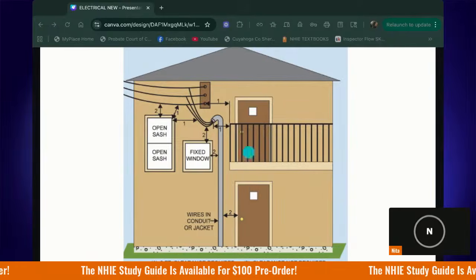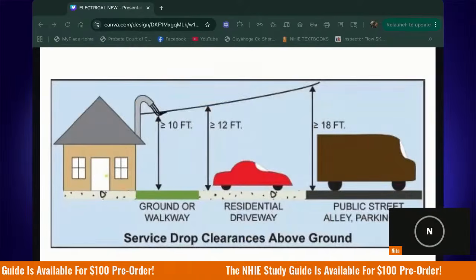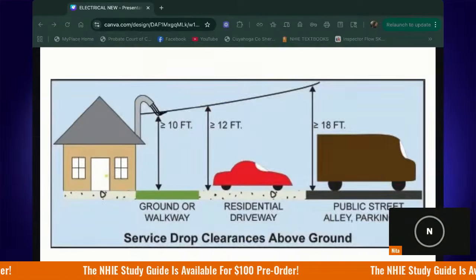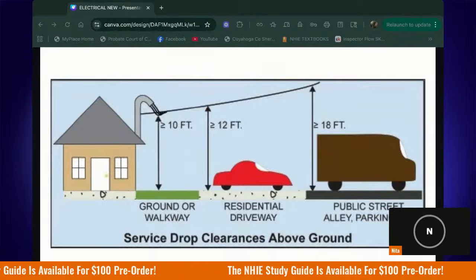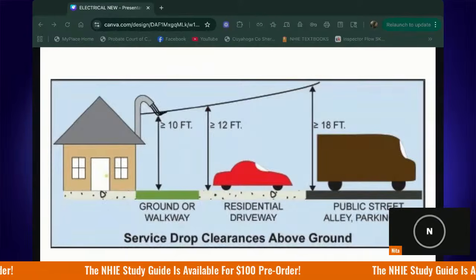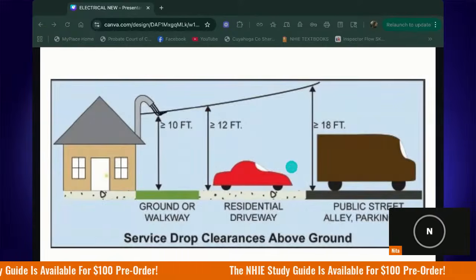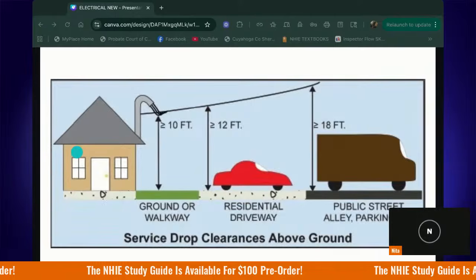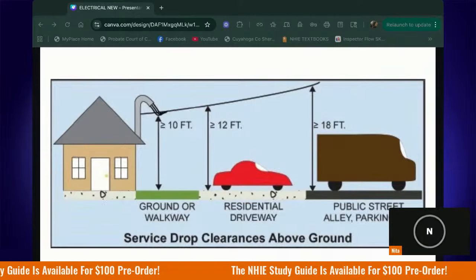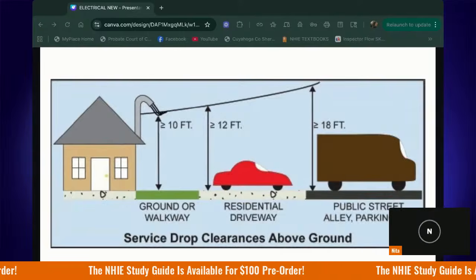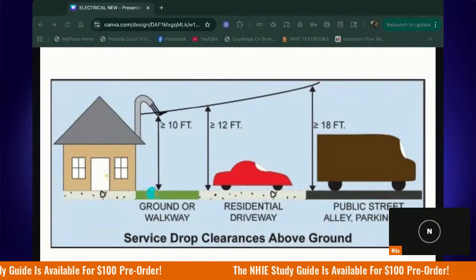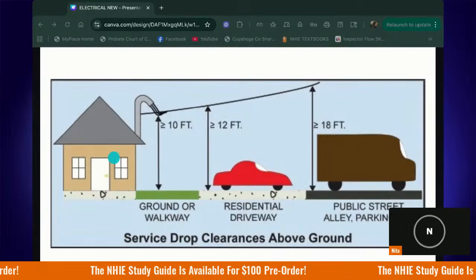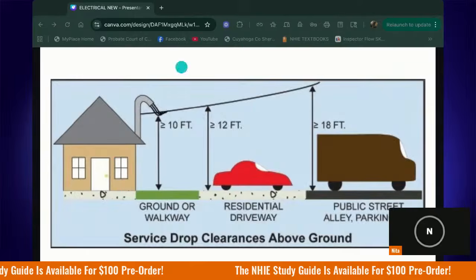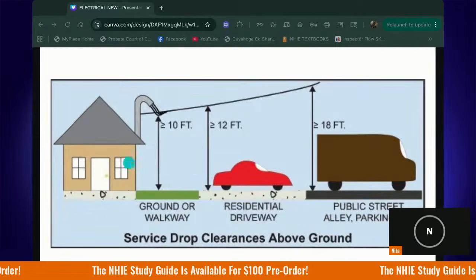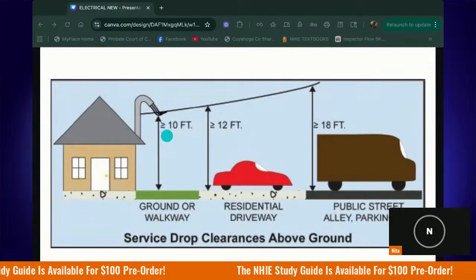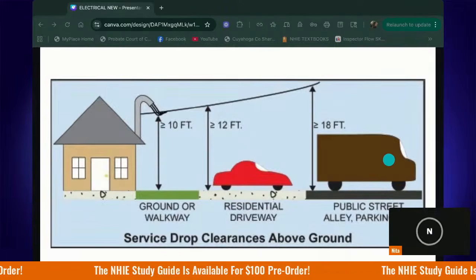And then lastly, as it relates to clearance, this is a test question, so you should memorize it. The service drop clearance is above the ground. So the minimum clearance when you're talking about the ground or a walkway is a minimum of 10 feet above the ground. So this is the lawn, the sidewalk, yards, 10 feet. And just think, this is the area closer to the house. Memorize this basically in the form of this diagram. The area that's closest to the house has the lowest clearance requirement. The further away that we get from the house, the higher it goes.